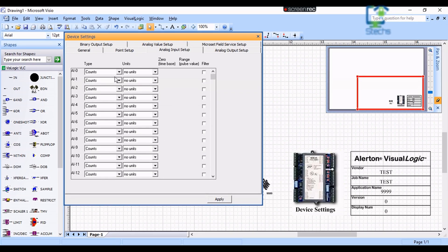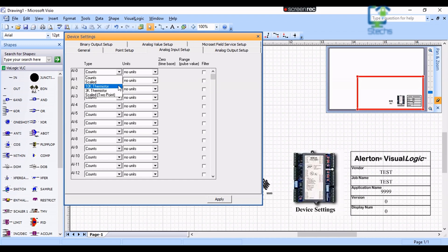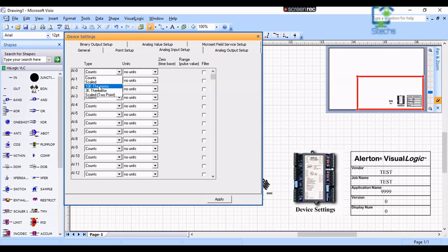When clicking on the type column of a particular input you can see 5 settings. The first one counts for digital inputs. The second one is Scaled, for scaling inputs for transmitter signals like 0 to 10 volt DC, 0 to 5 volt DC, and 4 to 20 milliamps, etc.